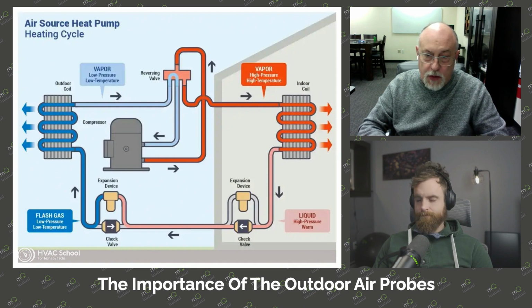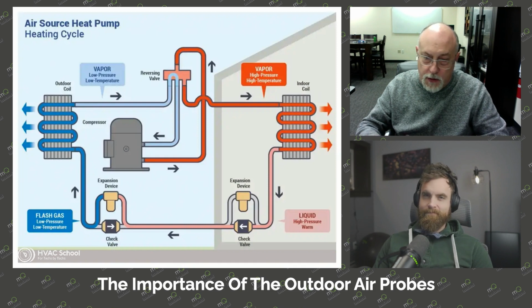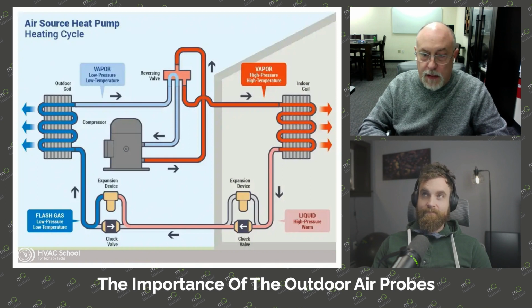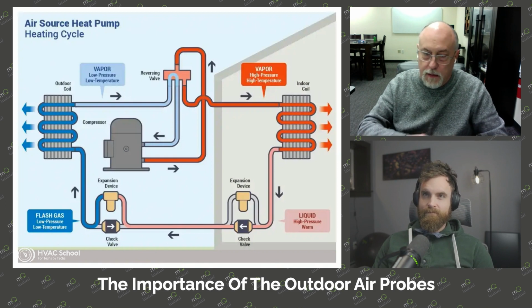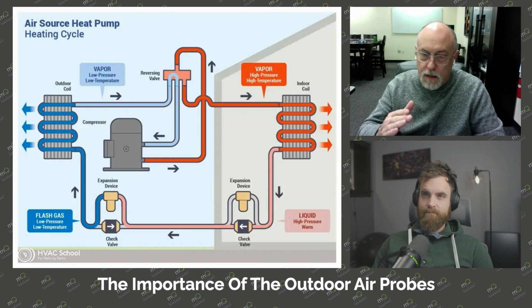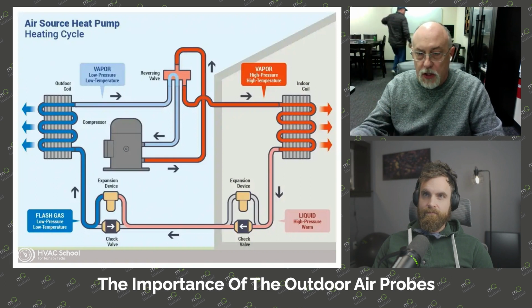So this, again, if you're talking a variable speed piece of equipment, turn the thermostat up at least 10 degrees above the indoor air temperature setting because we're in heating. We've got to turn this thing up. We've got to let that inverter get fully ramped up to high speed because we really can't evaluate the system at part load. So we're going to run the inverter fully up, let the system stabilize, make sure the charge is stable, and then we're going to be able to start to quantify how this system is actually performing. The key thing here is that it needs to be stable and we need to give this thing time.